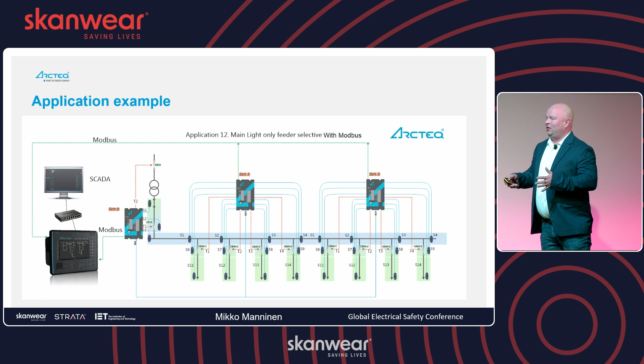If you have a tie breaker and a bus A, bus B, or main tie main, like they say in many places, you also trip the tie breaker, of course. Mitigation technologies. These ones here, left side, are low voltage, 690 volts. Resettable, it can be tested. So it can be tested 100 times. So if you do it every 5 years, I still don't promise that it will last 500 years. But you can really test it.